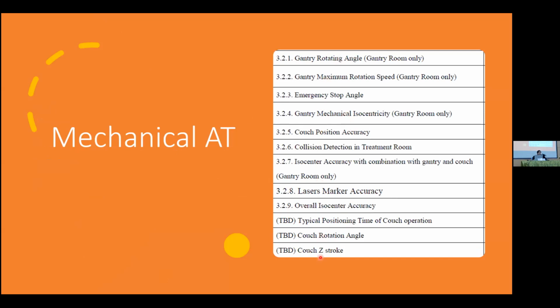The patient position is usually more complex than a photon one. Your gantry rotation, you saw how big these things are, so they do have sag. And an important thing to remember is not only is there a mechanical sag, like physically when the gantry is rotating, but those magnets themselves, when you're rotating, they slightly shift. And when they shift, the beam optics change. When the beam optics change, the spot characteristics change. So again, whatever you measure at one angle is not necessarily what you'll measure at a different angle. So it's important to test the different angles radiation-wise as well.